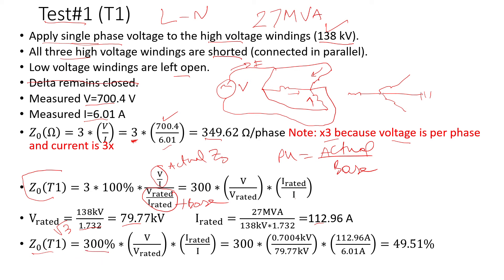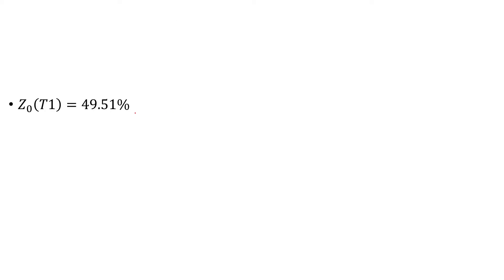Applying the equation: 300 × 0.7004 kV divided by 79.77 kV, times 112.96 amps divided by 6.01 amps — keeping units consistent so nothing cancels incorrectly. The zero sequence impedance obtained from Test One is 49.51 percent.